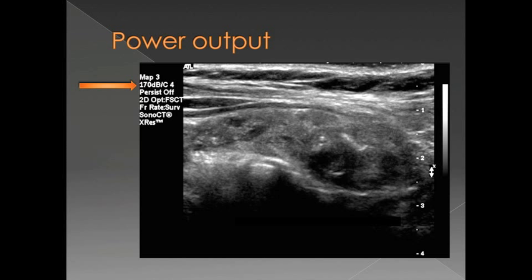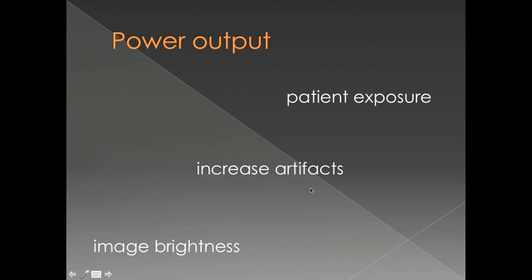Power output is essentially the amplitude or strength of the sound waves that are being sent out from the transducer. Most of the modern ultrasound machines are going to set this for you automatically, but just to let you know that this is something that you can set on some machines, and that if you do increase the power output, you can increase patient exposure, you can increase artifacts, and also this is another way to increase the brightness of the image, because if you send out larger, stronger pulses, you're going to be getting back larger echoes.